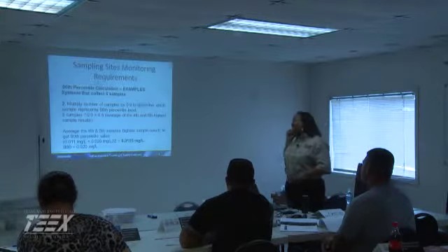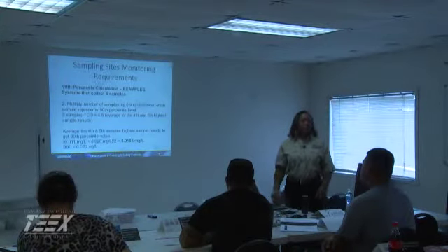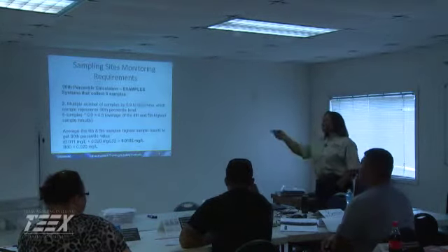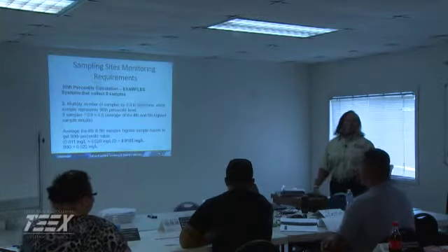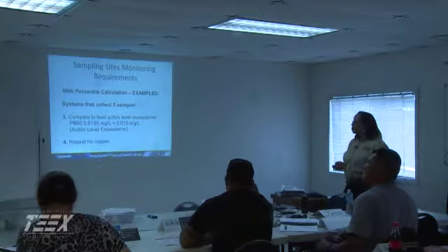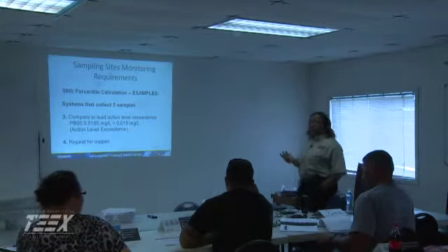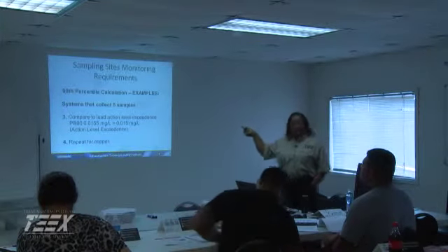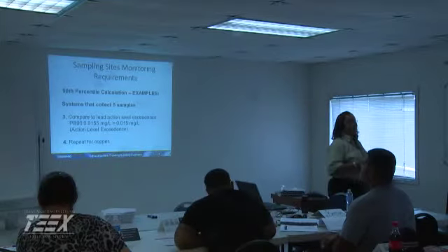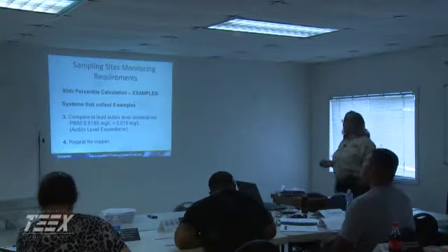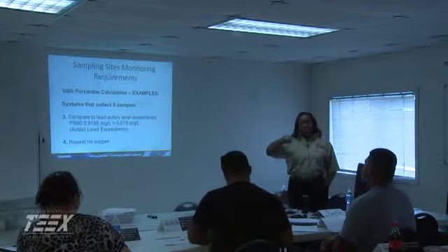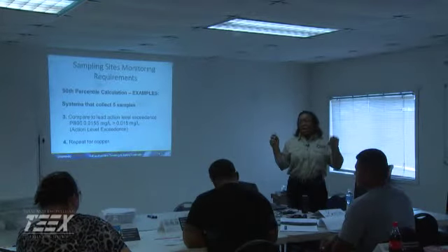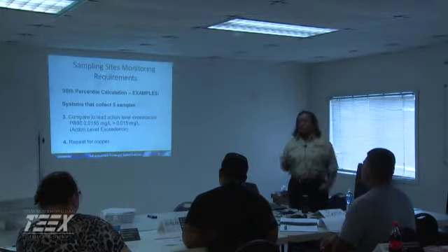0.015. Have I exceeded my action level? Yeah, that extra 5 on there. Yeah, and if you round, that's 0.02. I've exceeded. And that's what this is saying. Once you compare that to your action level, if it exceeded, 0.0155 is greater than 0.015, it's an exceedance. And so now I have to go into that additional analysis and water quality parameter testing every 2 weeks once I have my corrosion correction treatment in place.